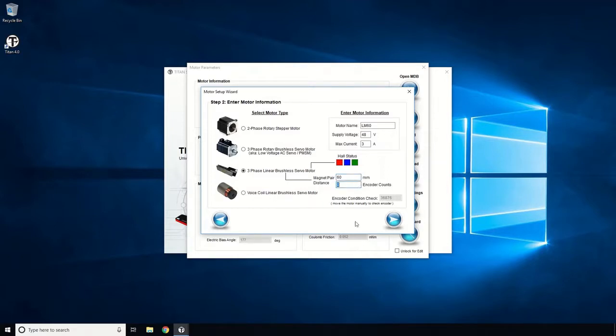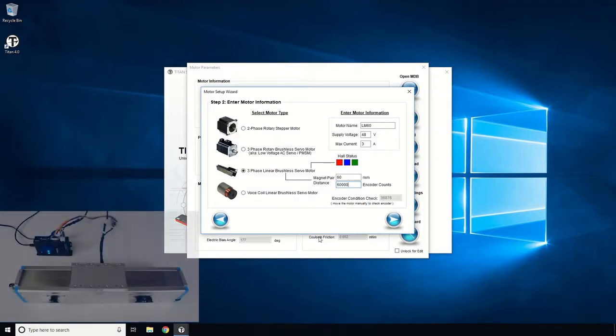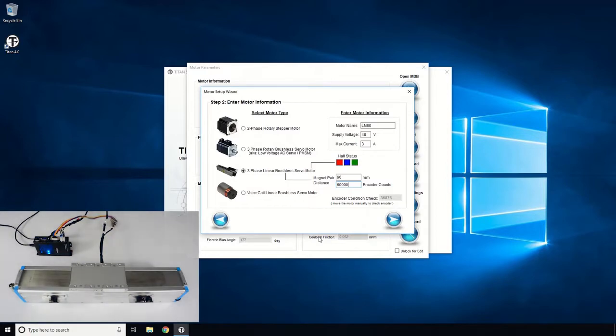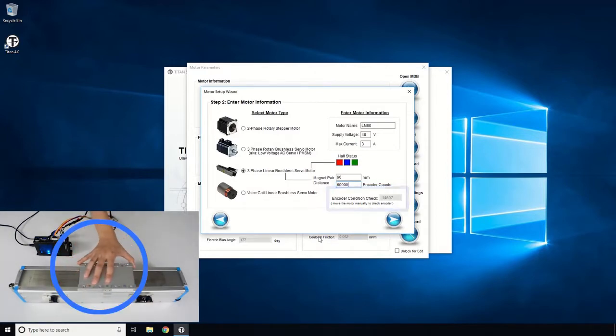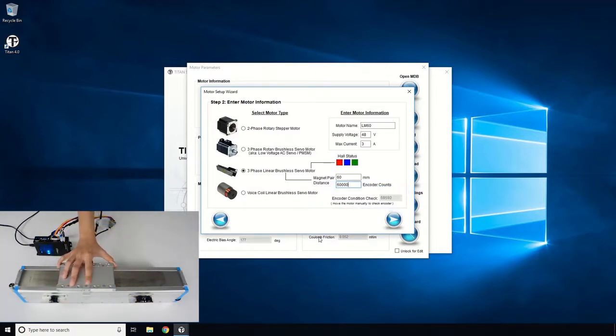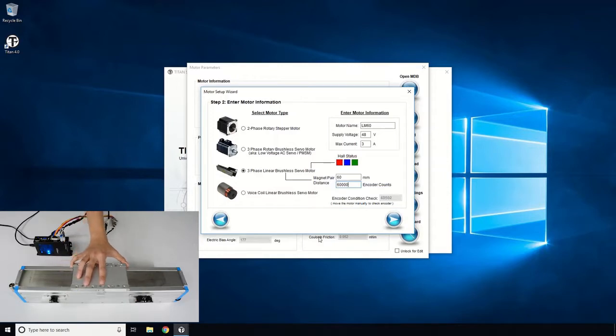The encoder resolution is 1 micron, so we will enter 60,000 for encoder counts, which is the encoder count for the magnet pole pair pitch. Next, let's check if the encoder is working by moving the linear motor manually and seeing the position change.